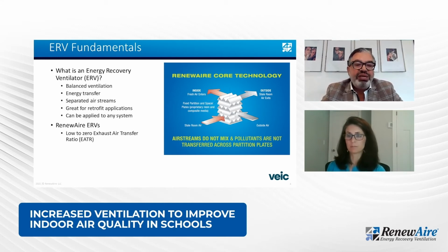And what's critical is when we say low to zero exhaust air transfer ratio, not all energy recovery systems, whether they're energy wheels or HRVs, are equal to this type of static plate core energy recovery equipment, because some of them can cross-contaminate as much as 12 to 18%. So using the right type of technology, and more specifically, making sure that you're transferring both latent and sensible energy becomes paramount over just transferring only sensible energy.